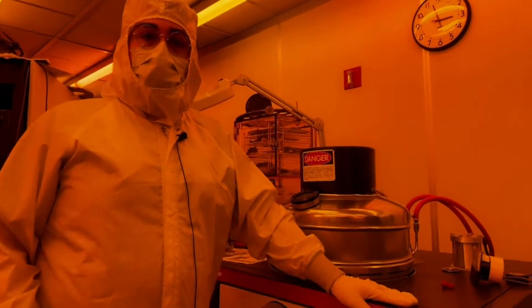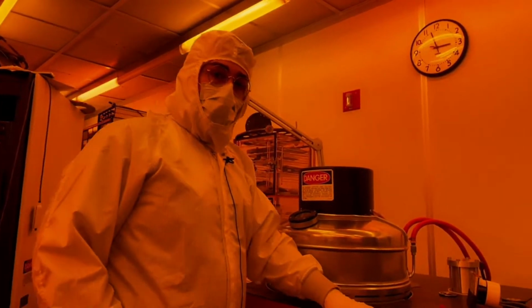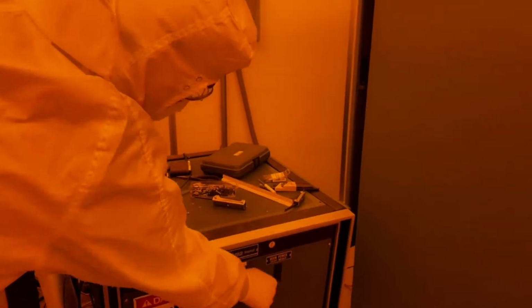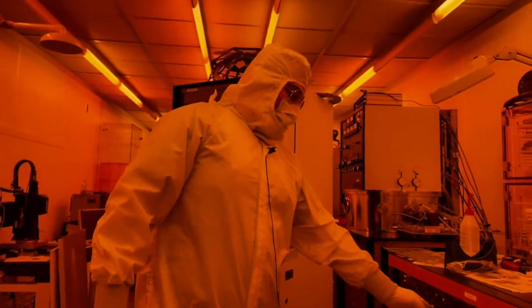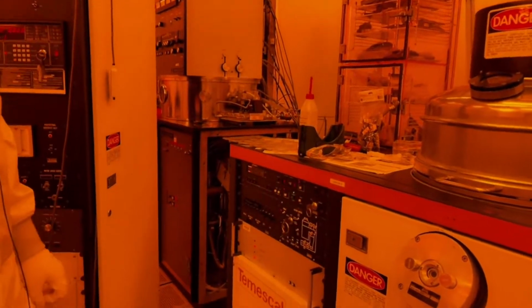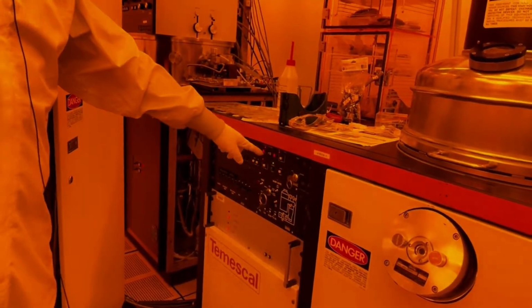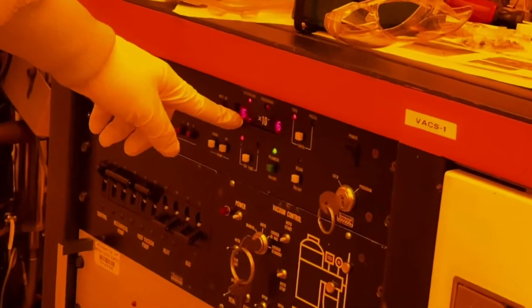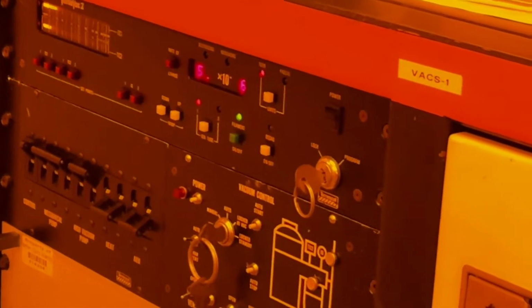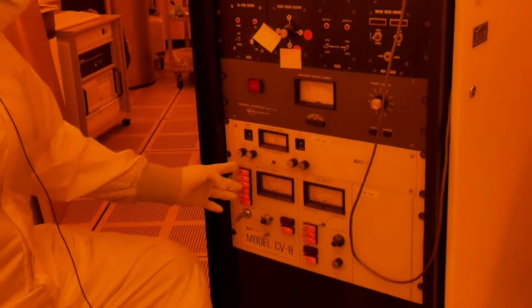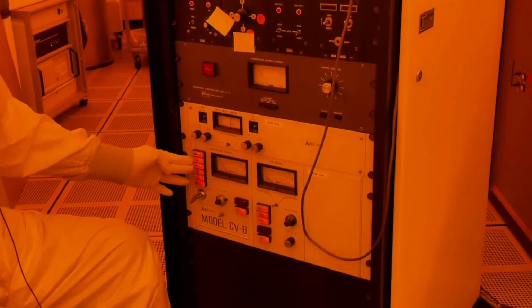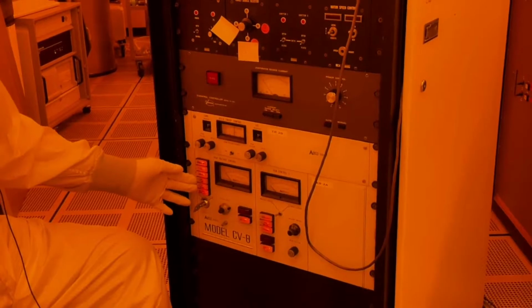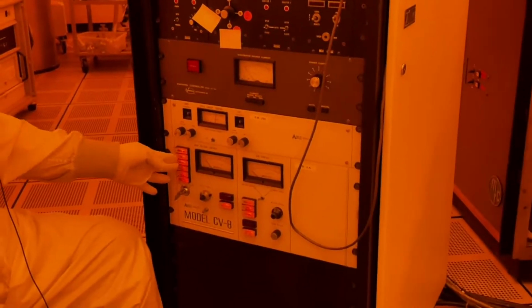So now we're going to do a test deposition of electron beam chromium. The first thing that we're going to do is turn on the high voltage power supply, the main circuit breaker. Next thing we're going to do is turn on our filament and check our chamber pressure. See, right now it's 5 times 10 to the minus 6 torr, which should be all right for doing a deposition. Next thing we're going to do is check that all of our interlocks are satisfied. So we're good here.